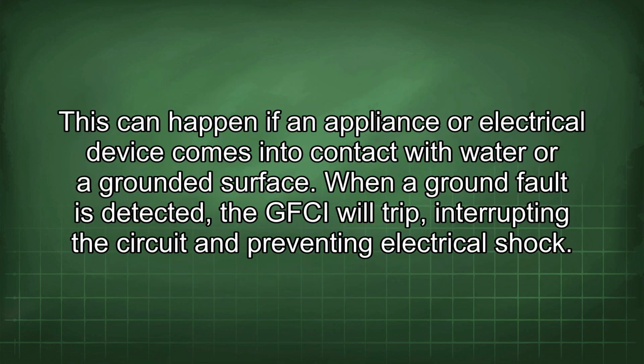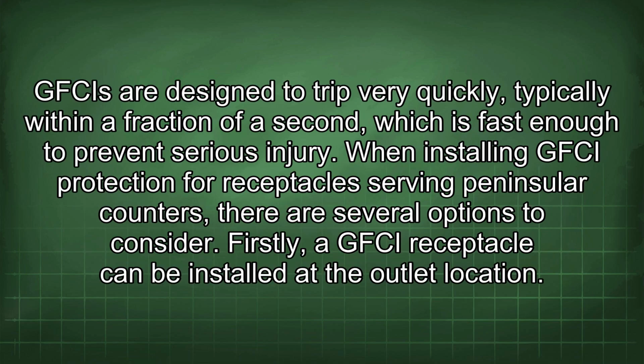This can happen if an appliance or electrical device comes into contact with water or a grounded surface. When a ground fault is detected, the GFCI will trip, interrupting the circuit and preventing electrical shock. GFCIs are designed to trip very quickly, typically within a fraction of a second, which is fast enough to prevent serious injury. When installing GFCI protection for receptacles serving Peninsular counters, there are several options to consider.